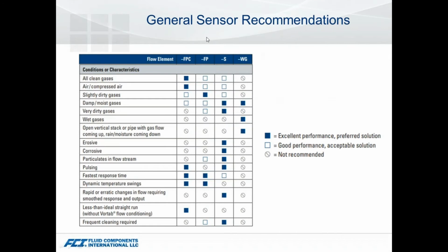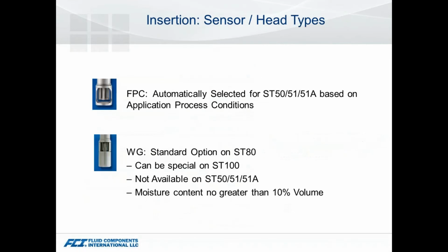So with all these different sensor types, we've got some general recommendations. Doesn't mean that you can't use a sensor in an application that it's rated good or not recommended, because sometimes conditions still say, hey, this is probably the best suited sensor for it. But we give you a little bit of a guideline, whether your process is dirty, whether it's got moisture in it, pulsation. Again, that FPC sensor handles pulsation very well. Response times. So just a guideline you can find in a lot of our manuals to brochures to help you figure out what might be best suited.